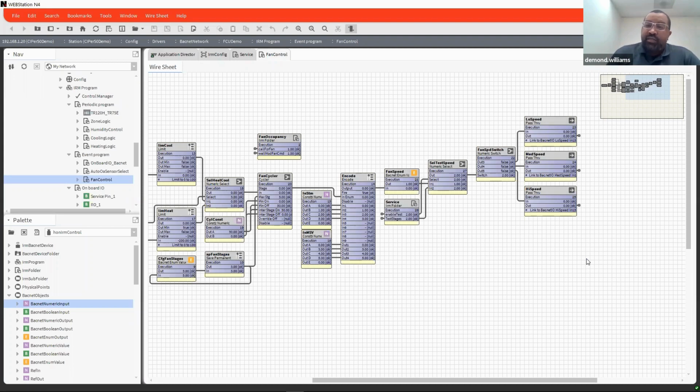So if your HVAC department is replacing a 3-speed fan in a fan coil unit, once everything is done, it cuts down on their time of having to get in touch with a building automation technician and having that technician simulate those different speeds to make sure that the fan was hooked back up correctly and everything is going to function the way it's supposed to.